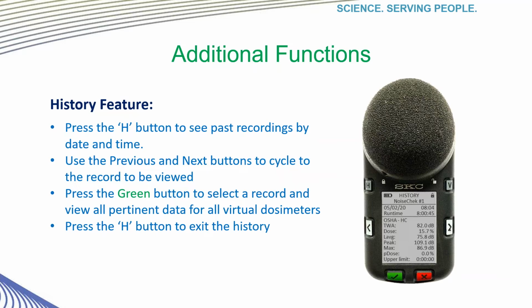At this point, you will see the sample summary on the display, as well as the date, the time, and the period of the run. Remember, when viewing the history information, you can use the left and right arrow buttons to view all sampling values for all virtual dosimeters that were set up in the dosimeter at the time of the run. It is not just one summary again, it is the individual summary for each dosimeter. When you're done viewing the history, simply press the H button again to exit that screen.